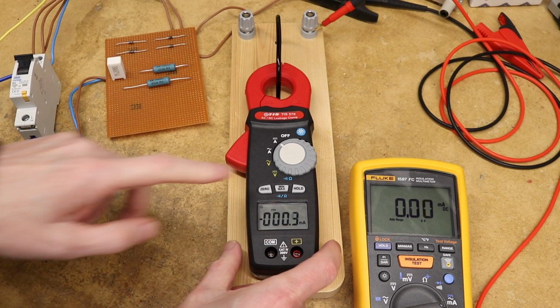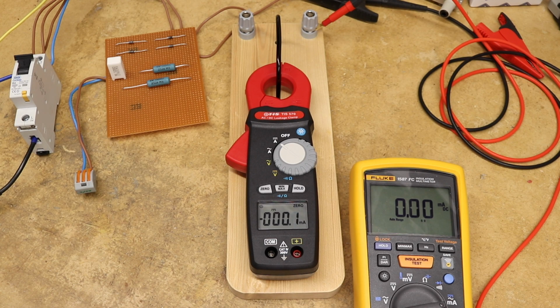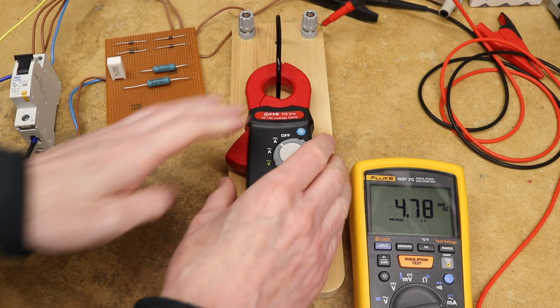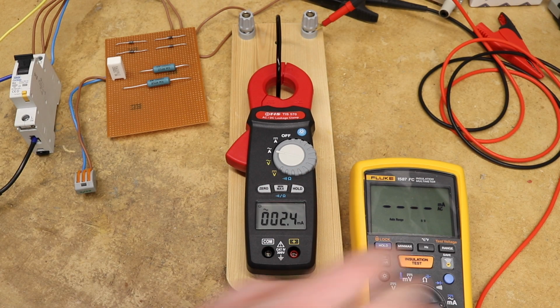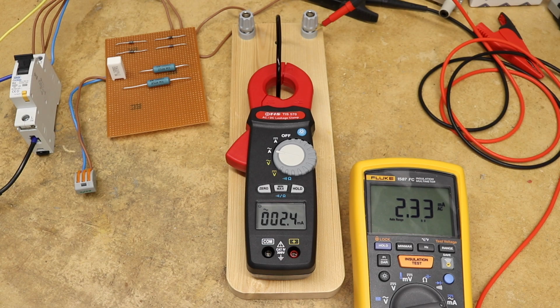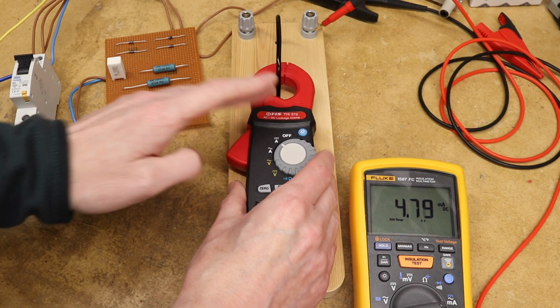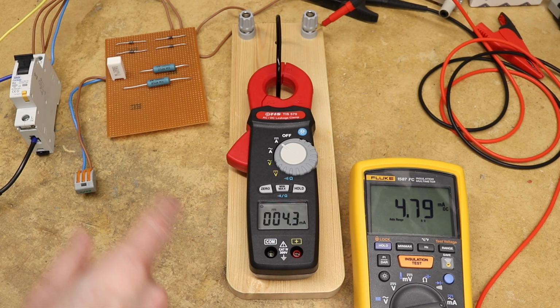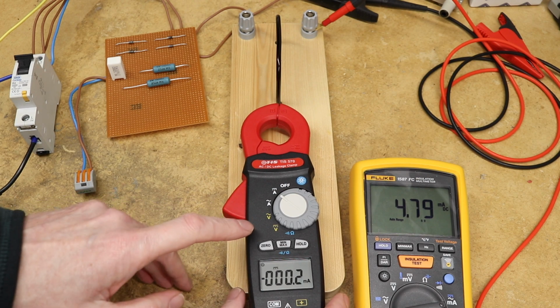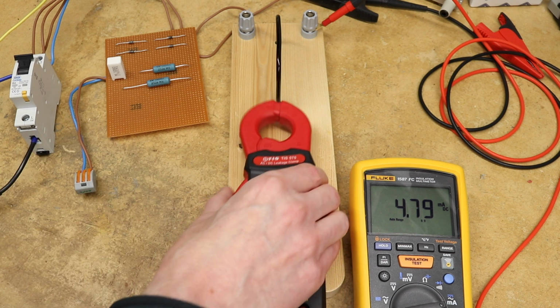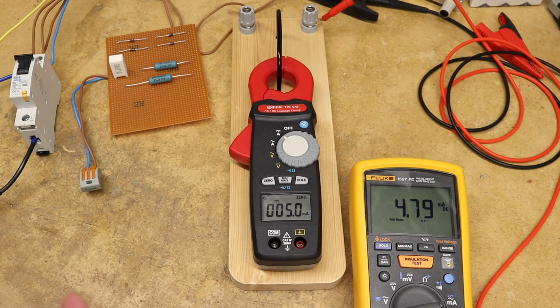So we are not quite zero, so we will put on our zero there. We will switch on, and you can see now our reading is 4.7 milliamps, 4.6 against 4.78, which is pretty acceptable. We can just flip to AC as well, so you can see there fairly comparable readings there. But we've also got, now the only downside to this is if I flick back to DC, you can see we're a little bit out because this isn't zeroed, and you can see I get a different value zeroing possibly when you're out of the circuit. So you can see I've gone the other way now, I've got 5 milliamps instead of 4.8ish, just because I've zeroed it in a different position.